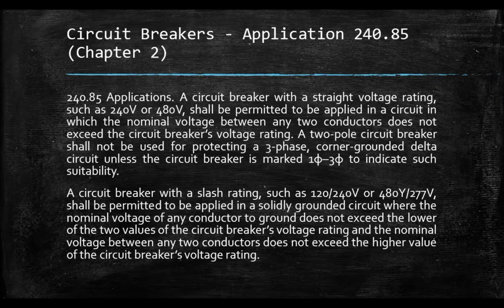Ang 3P daw na 120/240 volts breaker ay pwede siyang gamitin sa 208Y/120 systems, sa 120/208 volts, and 208Y/120 volt systems. Yung L-L voltage na 208 is less than the max rating, which is yung 240 of the slash rated breakers. Namomroblema lang tayo kapag nag-install tayo ng 120/208 volt slash rated breakers sa high leg deltas tsaka sa corner grounded deltas.